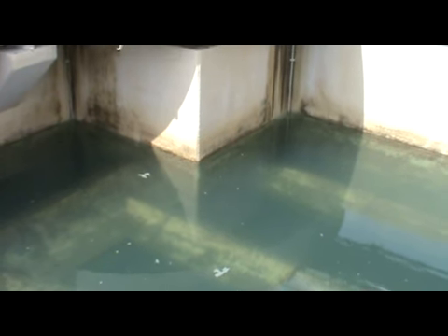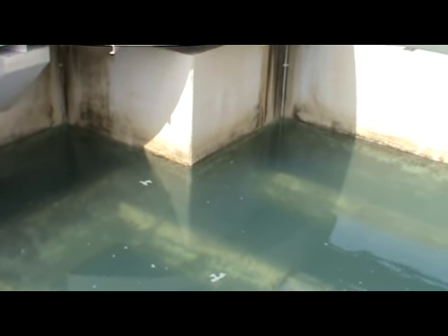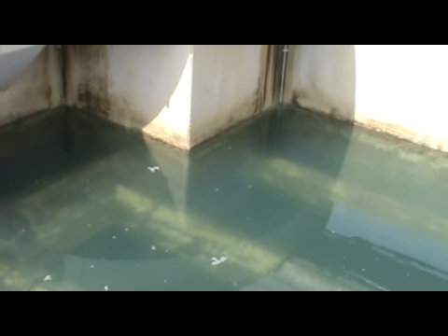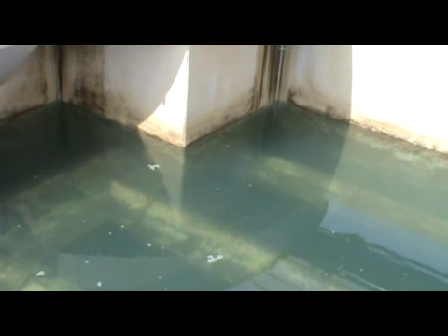So after the media has been expanded and all that stuff is flowed off to the washwater collection basins, then you go through a period where you bring the filter back into service. You still have not sent it to the effluent yet, to the treated water side, but you put the water back into the filter bed. You allow water to flow into it for a while, so it goes through a ripening period where those positively charged floc particles are allowed to kind of embed into the sand again. And then after you go through that certain amount of period, you return the filter to service.